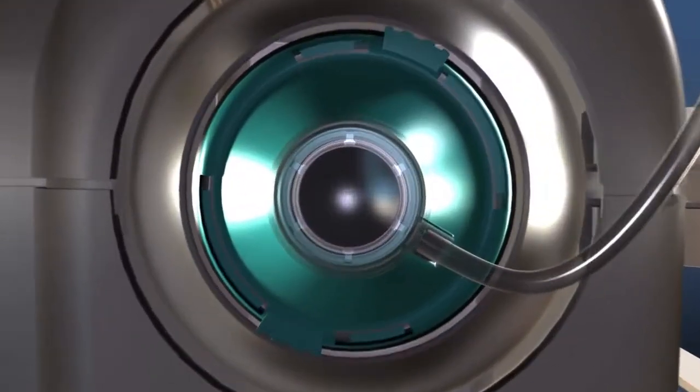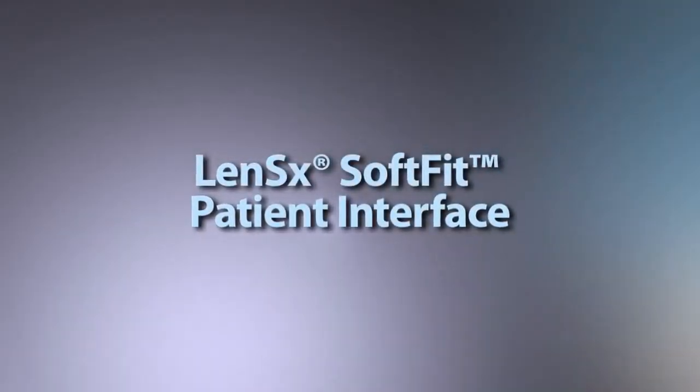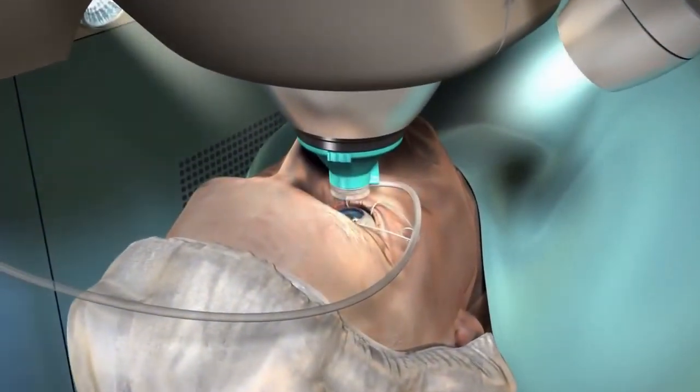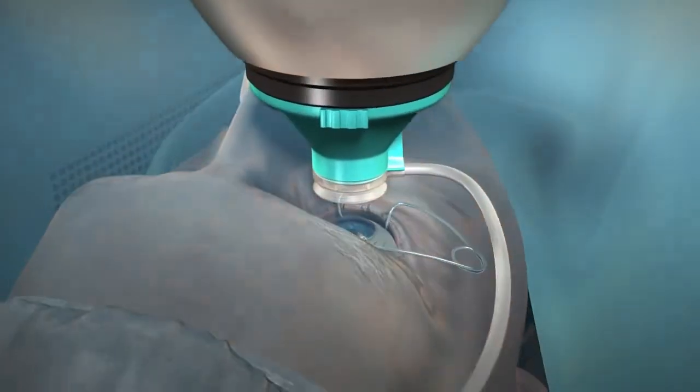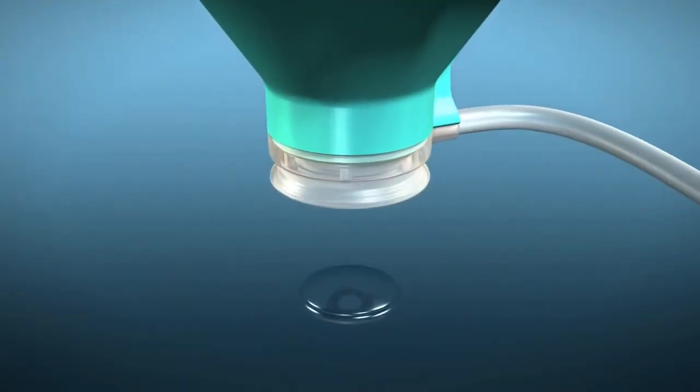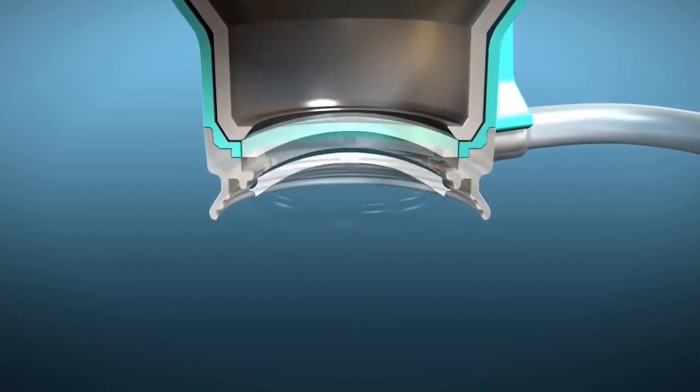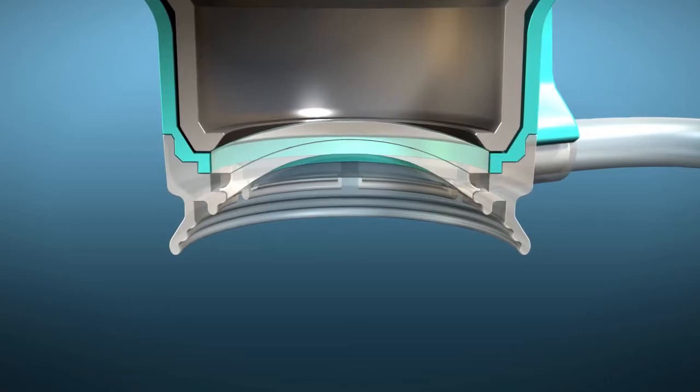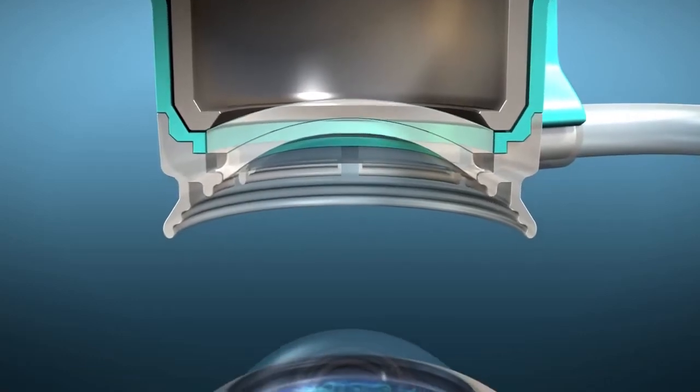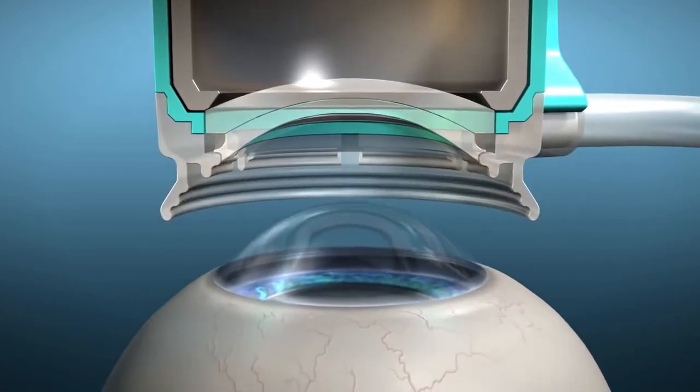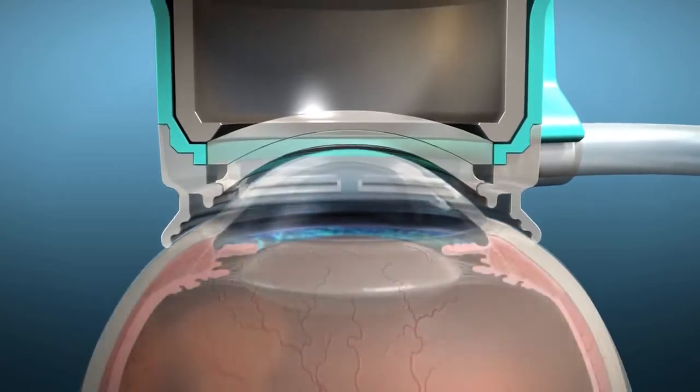The latest innovation to this advanced platform technology is the Alcon LensX SoftFit patient interface. This proprietary soft contact lens insert is gently placed into the patient interface. This allows the natural curvature of the cornea to conform to the lens insert, delivering a gentle, secure fit with minimal corneal distortion.